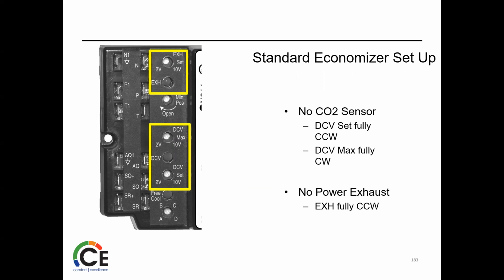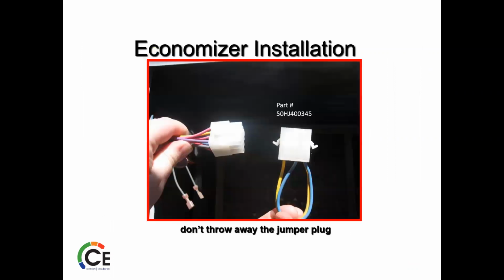The max is counterclockwise, so it's going to be open all the way. We're going to get full max, so you're going to get 10 volts. No power exhaust. So that's the basic operation. It's very rare that you ever use the EXH or DCV control. So just make sure they're open. If you're installing a field one, that silly little part there is your friend.